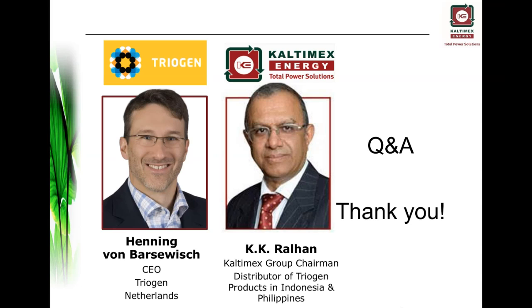We've got some equipment that's been in the field for 11 years running without problems. If you look at it as an engineer, it's actually pretty simple. It's largely heat exchangers, there's a couple of valves in there, some rotating equipment, but that's also not difficult to maintain. You need to do the right maintenance. When you compare it to an engine, it's almost got an infinite lifetime, because with a bit of maintenance, you're not wearing out anything. Rotating equipment is known to last for very long times. Steam plants run for 40, 60 years, no problem.